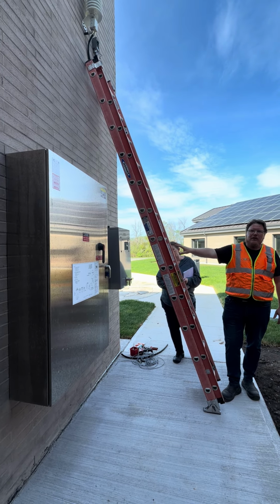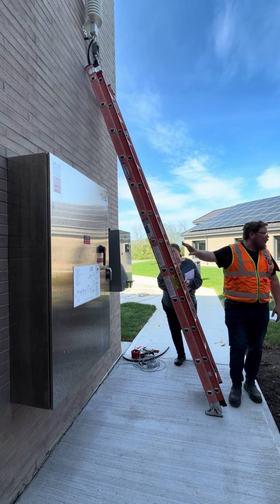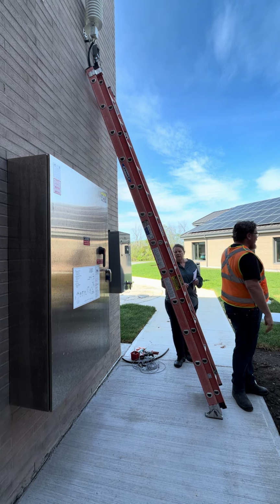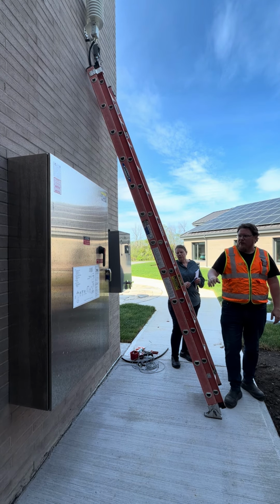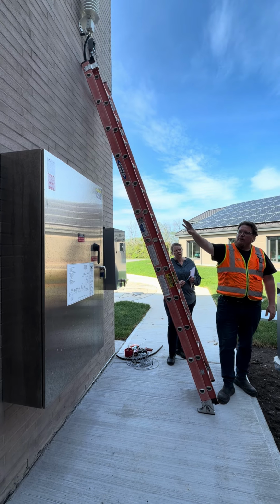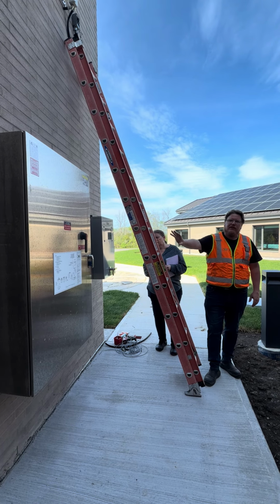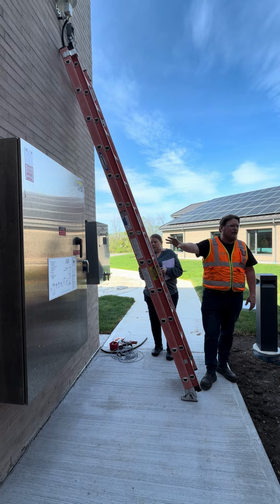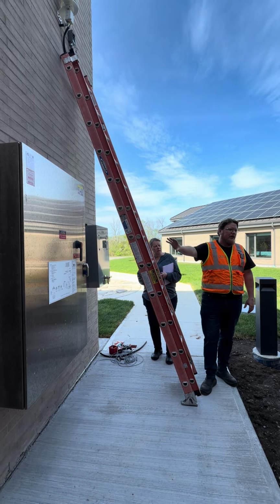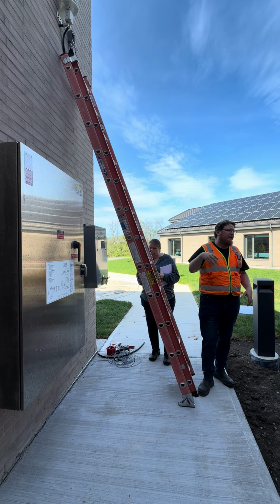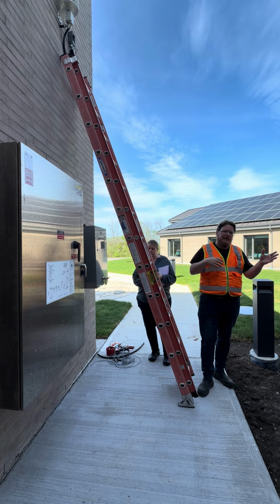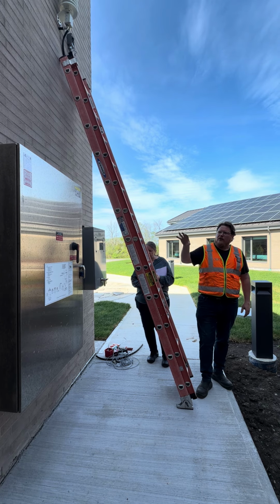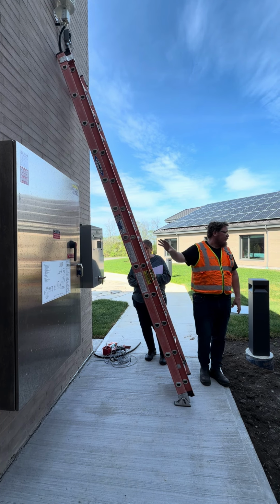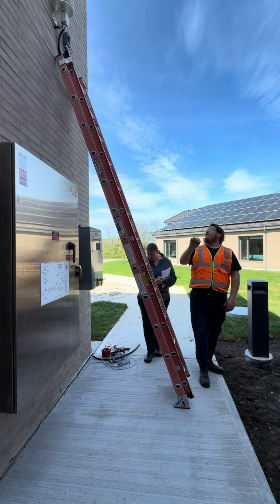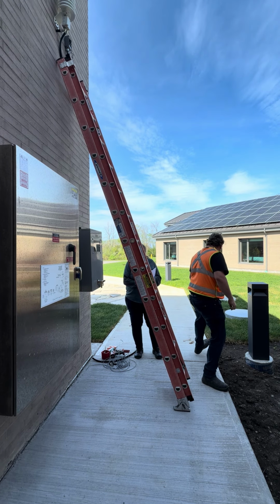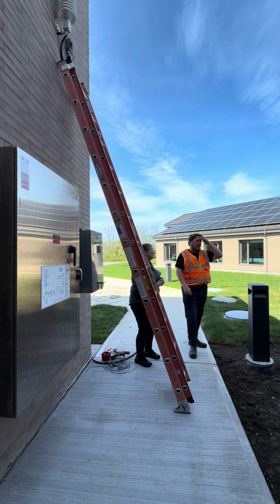It's adjacent to the metering because they always want to know where it is, and it's got to be lined up tight to a transformer, which is the distinction. This is a bigger enclosure because it also includes some of the monitoring control equipment for Hydro One. Because of the size of the system and the fact that we're connected to a lower voltage feeder, there is transfer trip provisions on this site, which means, where's that tower? Anyways, we'll look at it when we get to the roof.